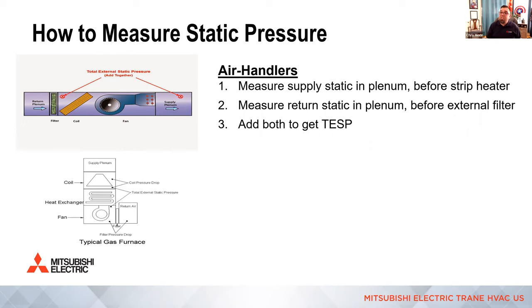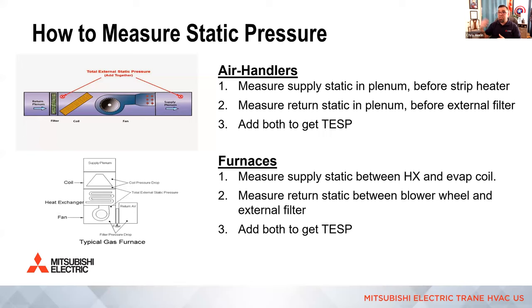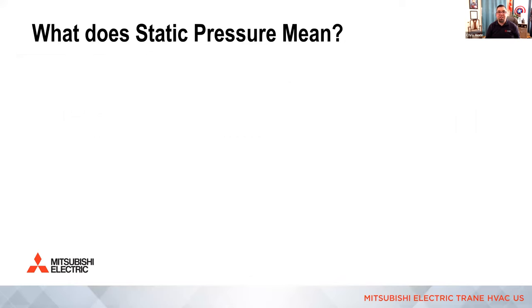And when you add these two numbers together, you would actually ignore the negative. It's on the return, obviously, return sucking air in, it's a negative pressure. Look at it as an absolute number and we're measuring differential pressure. So if we, as an example, measure negative 0.2 on the return and positive 0.2 in the supply, your total external static pressure in that example would be 0.40. So you can look at it as an absolute or as a differential, right? I won't get into how we used to measure it with actual water. That's another whole thing. We have much better, more accurate tools these days.